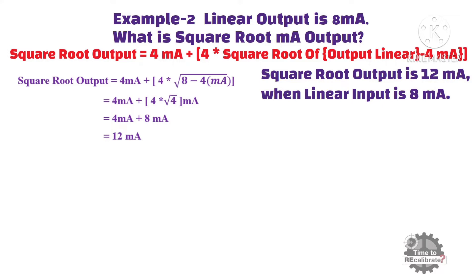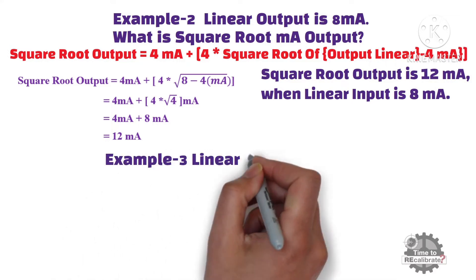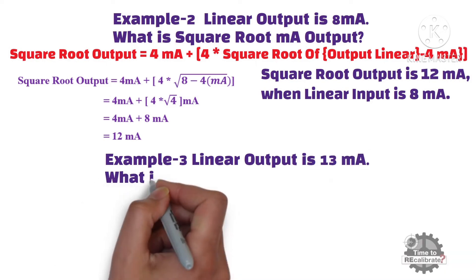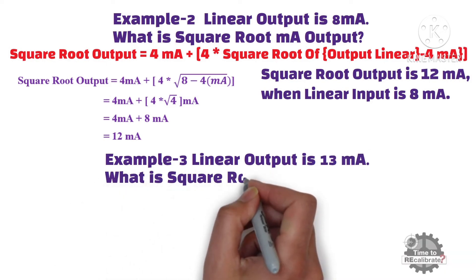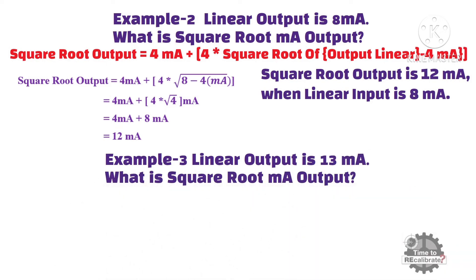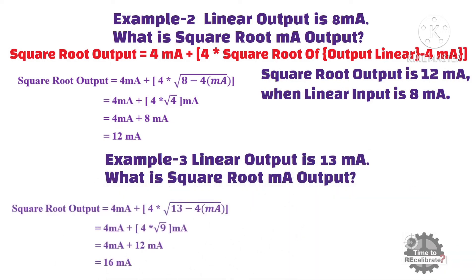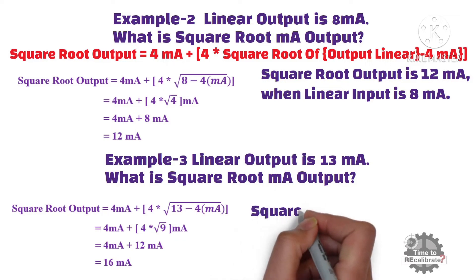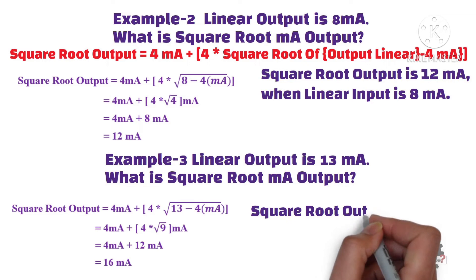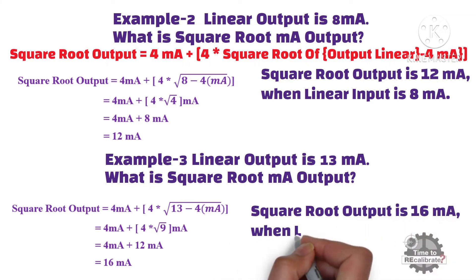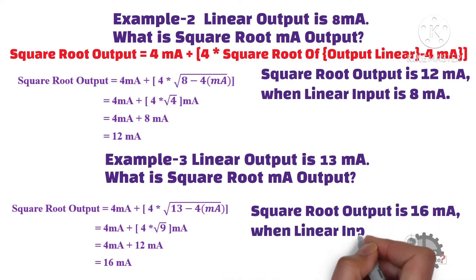Let's take a third example. If the linear output is 13 milliampere, what is the square root milliampere output? Put 13 milliampere into the equation and do the simple math calculation. It will give you 16 milliampere. So the square root output is 16 milliampere when the linear input is 13 milliampere.